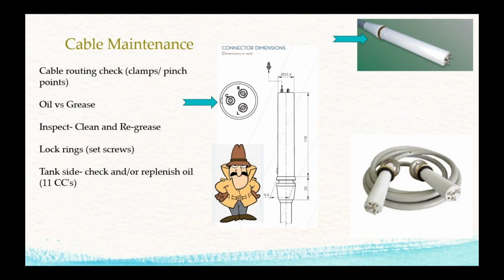So what I normally do is take my silicone grease, I wipe all the old grease off, usually isopropyl alcohol gets it nice and clean. If you talk to 15 different imaging engineers, they have 15 different ways to put grease on a candlestick. But we all have our way. I just put a big glob between all the pins. I take a popsicle stick and rub down the shaft of the high voltage cable. What we're trying to do there is push all the air out of the system so we have no arcs inside. That silicone grease is an insulating grease, and it also dispels air. And so that's part of the routine maintenance.